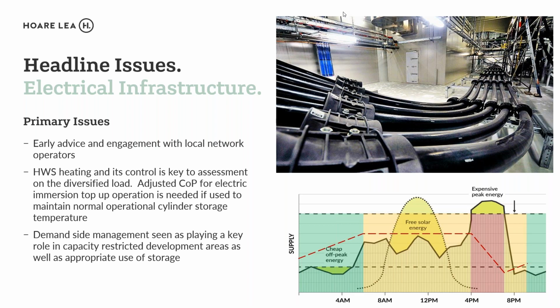Controls on the electrical side may also be a thing that will come in, where it's demand controlled. Particularly if you are looking at part top up through electric immersion, and I'll come on to that later, basically the switching in of electric immersion to do hot water generation over and above the generation that's done through heat pump may actually be time strapped with regards to the cost of when that kicks in, but also how it's demand side adjusted to make sure you don't go over the peak capacity of the incoming supply, if diversity has been taken into account. So that's one of the key issues: looking at how you control electrical usage in the building when you are providing everything through electrical for heating, electricity, sorry.